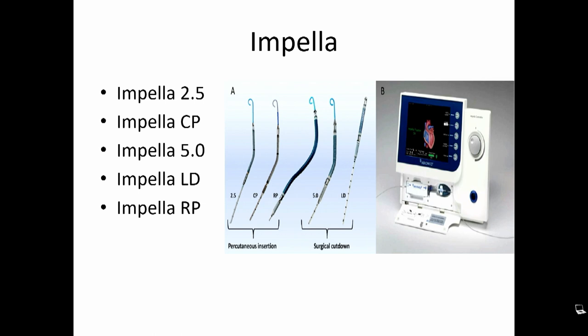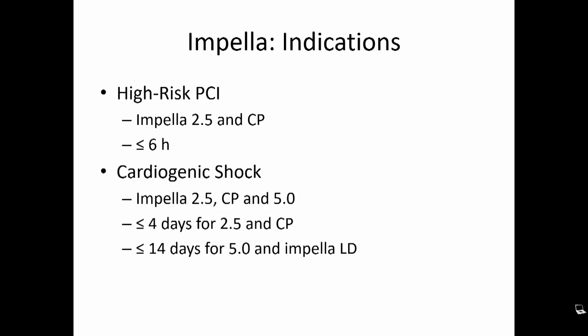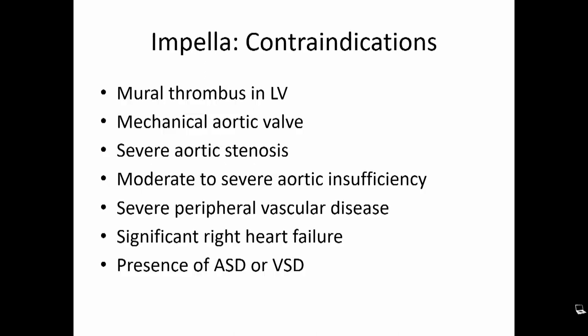The second family of pumps is Impella. We have multiple types: Impella 2.5, CP, 5.0, LD for left-side support, and RP for right-side support. It is approved for high-risk PCI up to six hours, cardiogenic shock up to four days for Impella 2.5 and CP, and up to 14 days for Impella 5.0 and LD. Contraindications include LV thrombus, mechanical aortic valve, severe aortic stenosis, moderate-to-severe aortic insufficiency, severe peripheral vascular disease, significant right-side failure, and the presence of ASD or VSD.